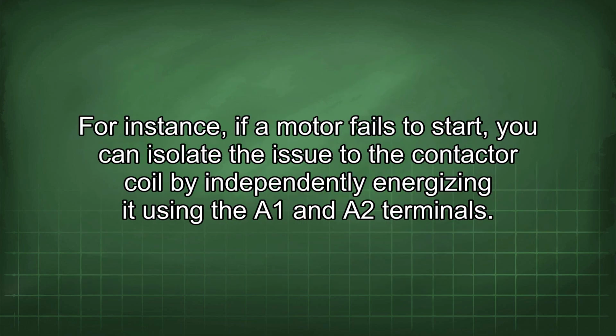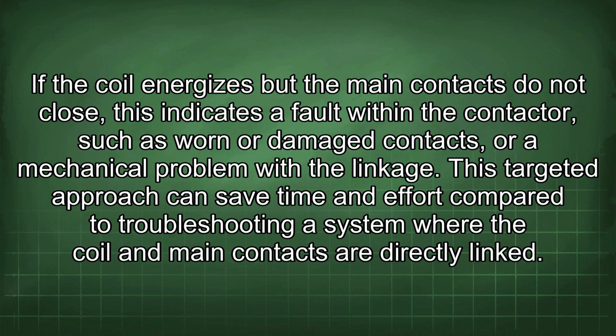For instance, if a motor fails to start, you can isolate the issue to the contactor coil by independently energizing it using the A1 and A2 terminals. If the coil energizes but the main contacts do not close, this indicates a fault within the contactor, such as worn or damaged contacts, or a mechanical problem with the linkage. This targeted approach can save time and effort compared to troubleshooting a system where the coil and main contacts are directly linked.